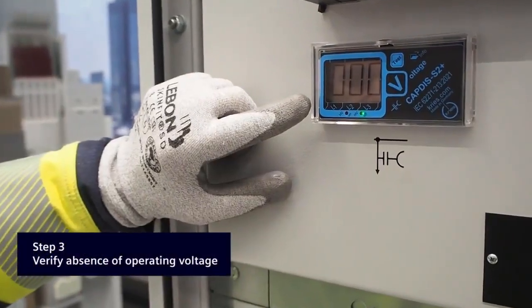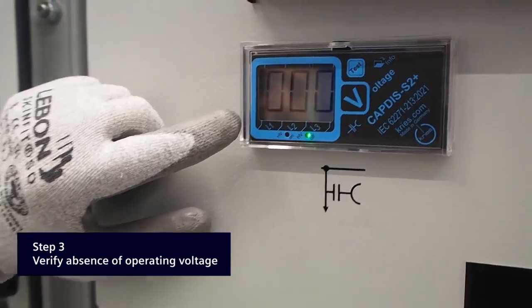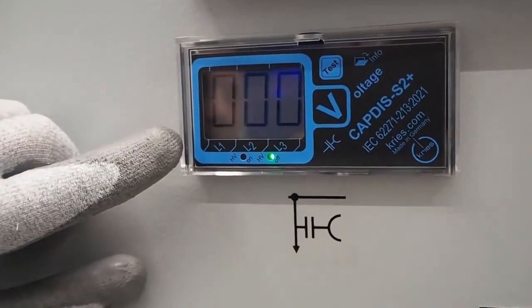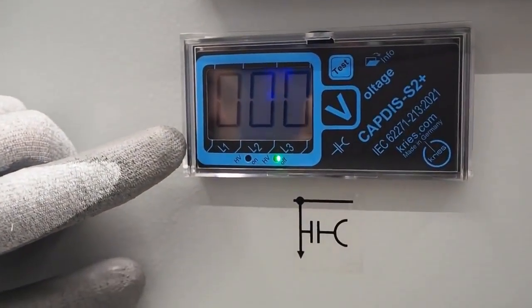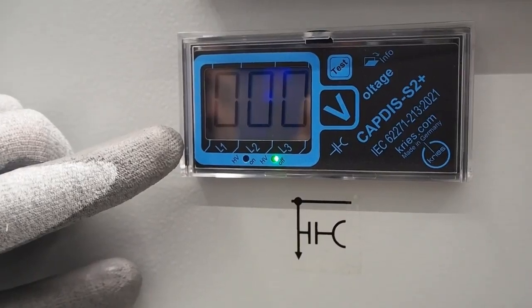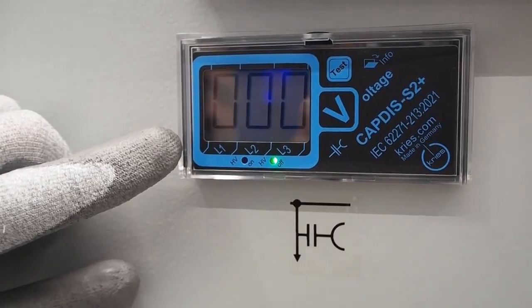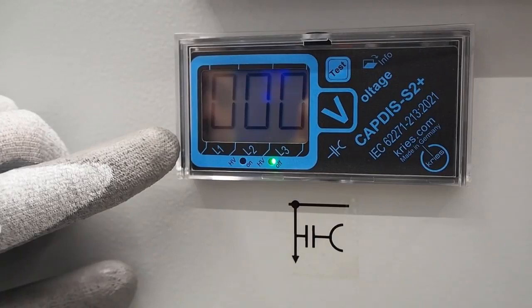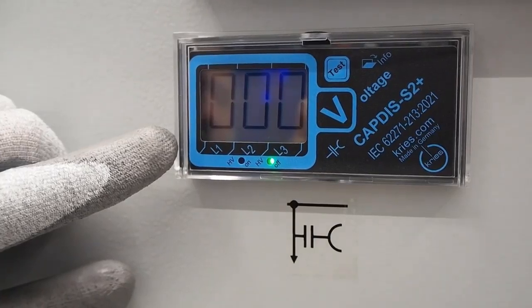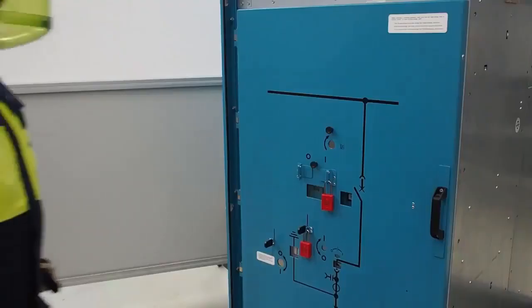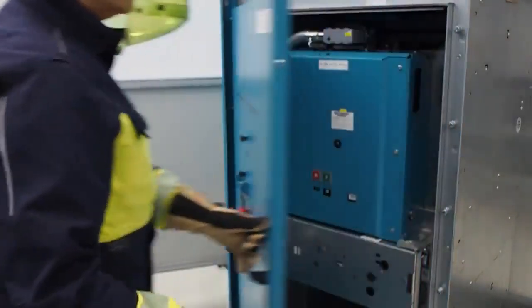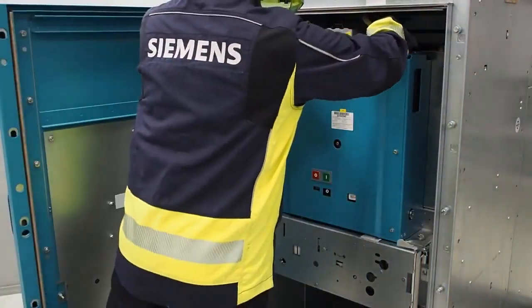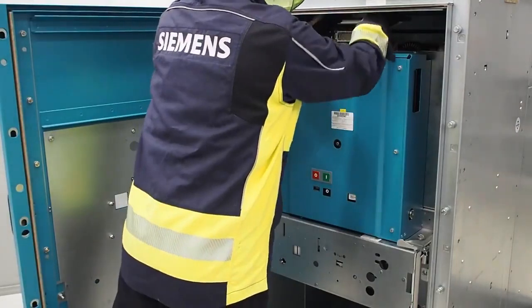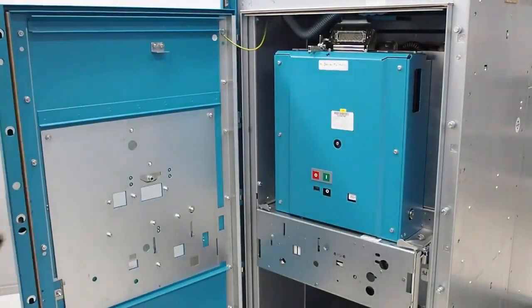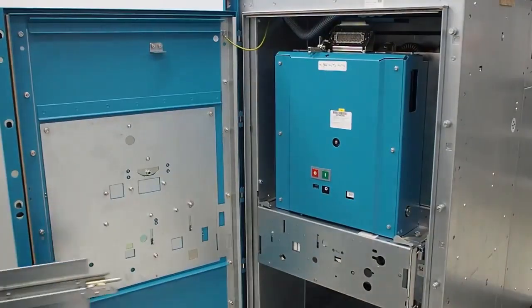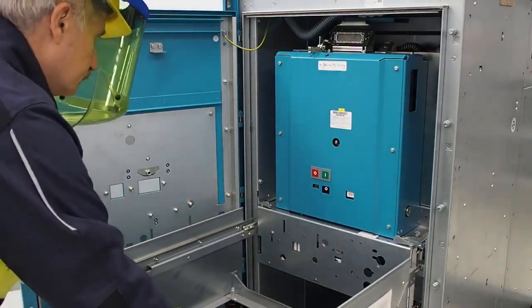Now you will verify safe isolation from the operating voltage. For feeder and busbar applications, check for voltage via the integrated capacitive voltage detection system. If the integrated capacitive voltage detecting system is not available, proceed as follows. First, open the high voltage door and disconnect the low voltage plug. Then, remove the circuit breaker from the panel with a service truck.